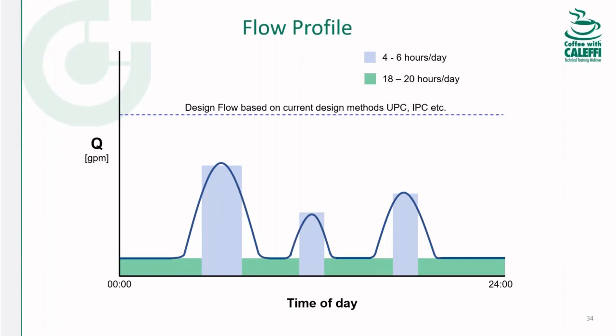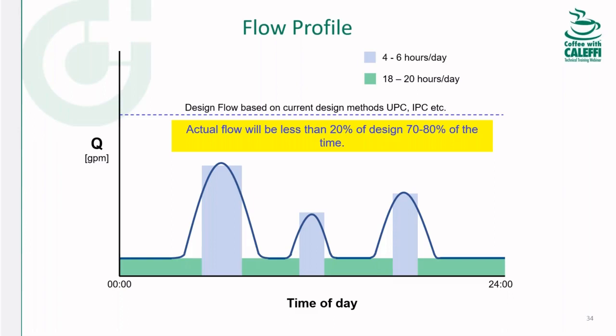Also keep in mind that when you're sizing your booster, if you're using the charts for the plumbing codes, which is required in a lot of states, that design flow you're coming up with is representative of something like the dashed line up there, which you're never going to achieve. So when you select your pumps, you want to use multiple pumps, with the understanding that your actual flow will be less than 20% of this design flow for 70 to 80% of the time.